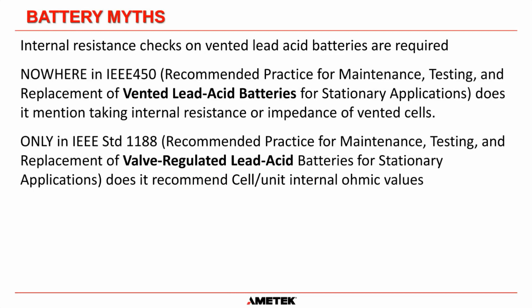Basically, it does nothing for a vented lead acid battery, because you'll see the plates degrade much quicker with your eyes than with a cell corder or with a Midtronics, whatever device you're using. The only thing really that a Midtronics or a cell corder can do for vented lead acid batteries is see if there's a plate short or an open circuit cell, which is very rare. So internal resistance checks are not required or recommended on vented lead acid batteries.